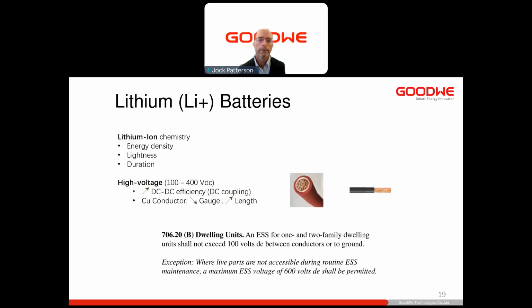Now on to the equipment. For batteries, we're going to just focus on lithium-ion batteries because they're popular and they have a relatively flat discharge curve. They're high energy density. They can do many cycles, and they're relatively light, even though they are not light in a general sense. We are going to look at high voltage versions of these. Why? Because that's becoming more popular and people might not be as familiar with them. So instead of your regular 48 volt system, we're talking 100 to 400 volts.